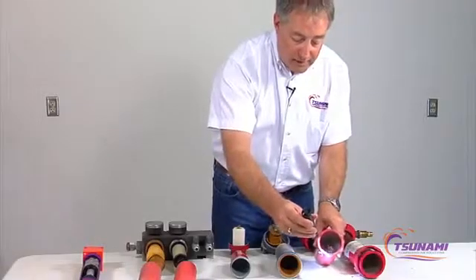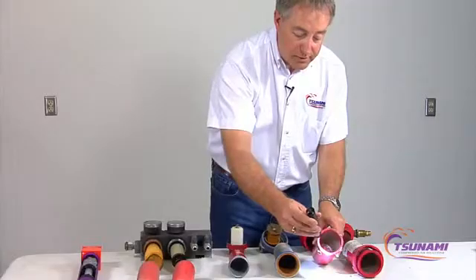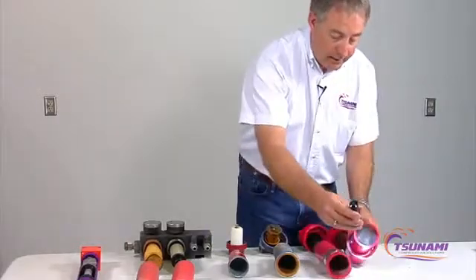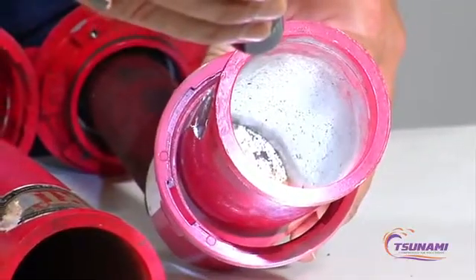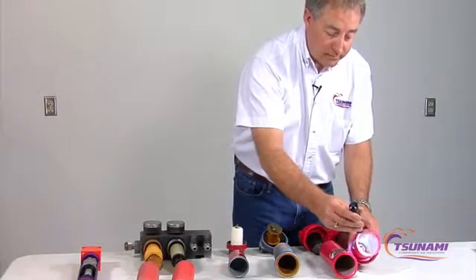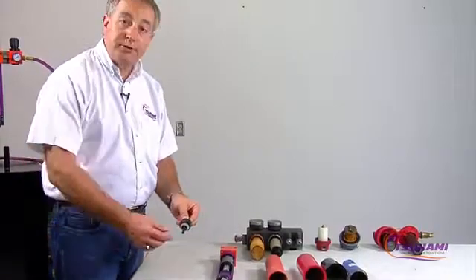Here's another die cast housing. The drains sit right on the very bottom, so if there's any contamination in there, it goes right to the drains, and the drains will fail eventually. And some of the coalescing filters, again, they're uncoated on the inside, and also they have no automatic drains on them. One thing guaranteed about a float drain, it will fail. It's just a matter of time.